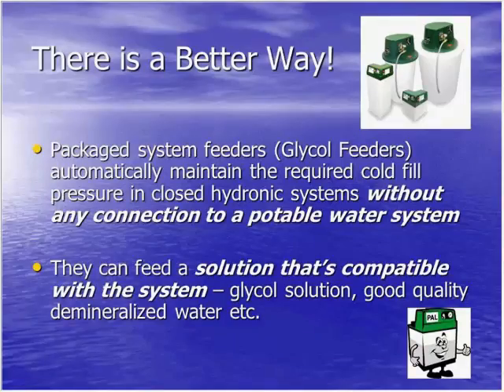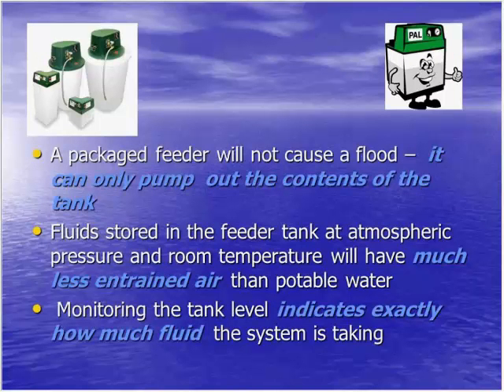A package system feeder will not cause a flood. Only the contents of the tank can be pumped into the system if something were to happen. So if something were to happen, you may only find a few gallons of fluid on the floor, not several hundred or thousands of gallons if that fill valve was left open. Fluids stored in the feeder at atmospheric pressure and room temperature will have much less entrained air than potable water.